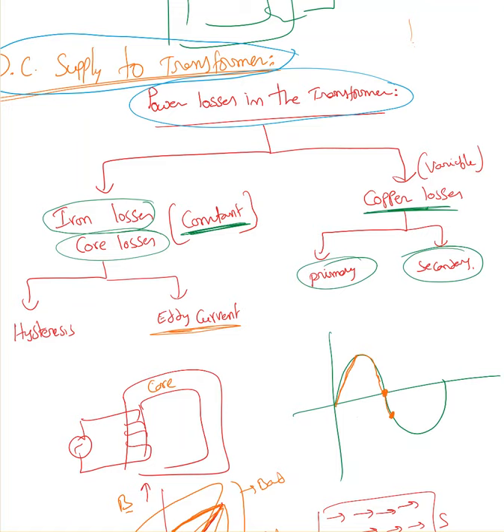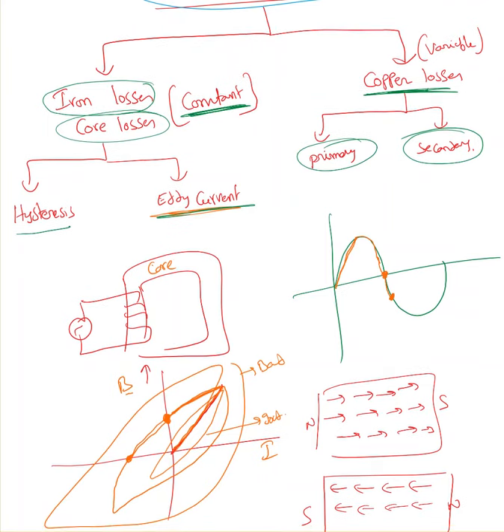When it comes to iron losses, there are again two types: hysteresis losses and eddy current losses. Hysteresis losses are core losses that happen inside the core. If you take a magnetic core material, when it is not magnetized, all the little magnets are in different directions, so magnetically the material is neutral and shows no magnetism.